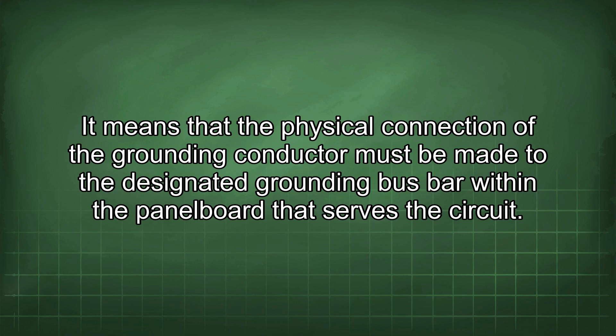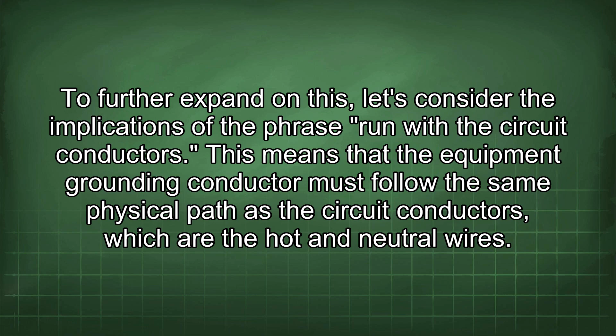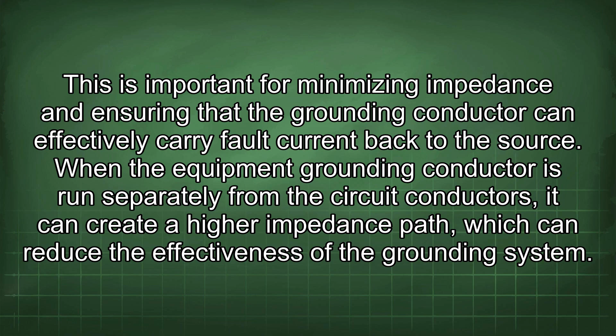To further expand on this, let's consider the implications of the phrase run with the circuit conductors. This means that the equipment grounding conductor must follow the same physical path as the circuit conductors, which are the hot and neutral wires. This is important for minimizing impedance and ensuring that the grounding conductor can effectively carry fault current back to the source. When the equipment grounding conductor is run separately from the circuit conductors, it can create a higher impedance path, which can reduce the effectiveness of the grounding system.